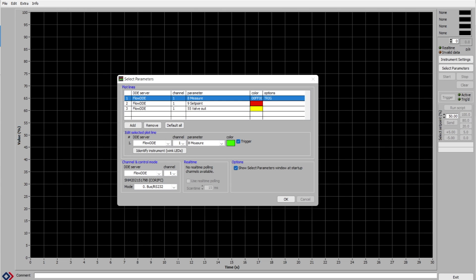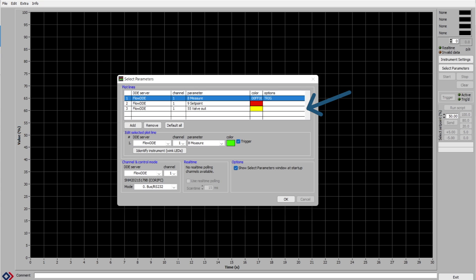When you first open FlowPlot, this is the dialog box that appears. There are three lines that will be graphed. The first green one is the measure output showing the flow in the system. The red is the setpoint output, which is what we are controlling with the FlowPlot software, and the yellow is the valve output. Also in this box, in the bottom left hand corner, you can see in the channel and control mode section, I have RS232 selected as my mode of communication.